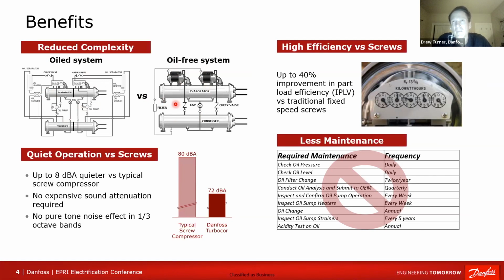But the other thing that the technology drove, one of the main other goals that came along with the invention of this compressor, was to also significantly improve the efficiency versus what was out there at the time. And part of getting there was the centrifugal compression, both the centrifugal compression itself as well as the 2 stages of it that's built into this design. And then the permanent magnet motor, which also improved the efficiency, along with what I haven't mentioned already, the integrated variable speed drive. So every Turbocor compressor has an integrated variable speed drive. But what that means in terms of efficiency is roughly a 40% improvement over the technology that's out there today. And that's versus HFC constant speed screws.